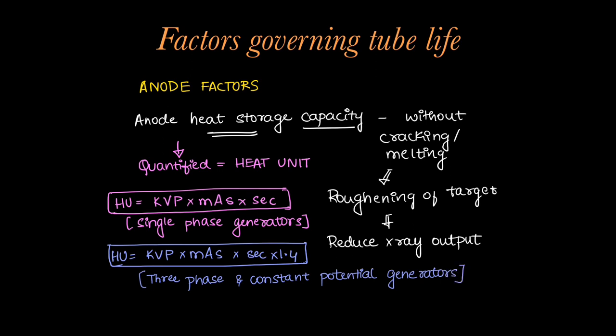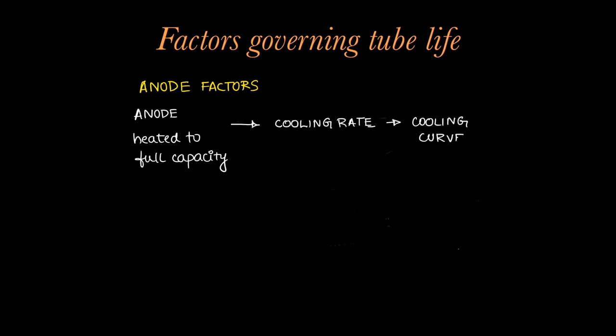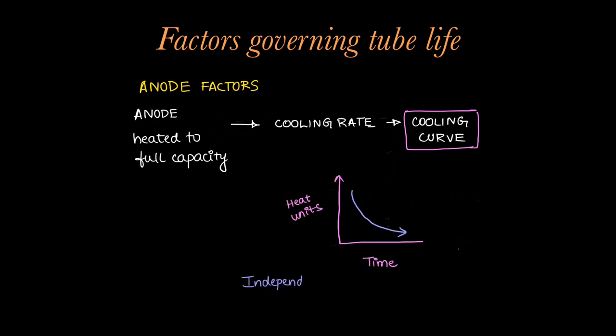Speaking in general, the average heat storage capacity of a typical anode will be 25 kilo heat units. Once the anode is heated up to its full capacity, it has to be cooled down before the next exposure. The cooling rate is given by a cooling curve which is drawn as heat units against time. This is independent of anode rotation time.